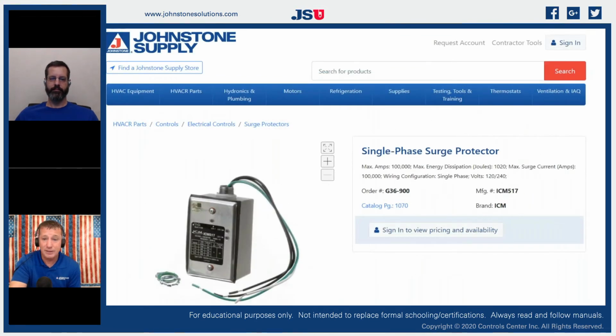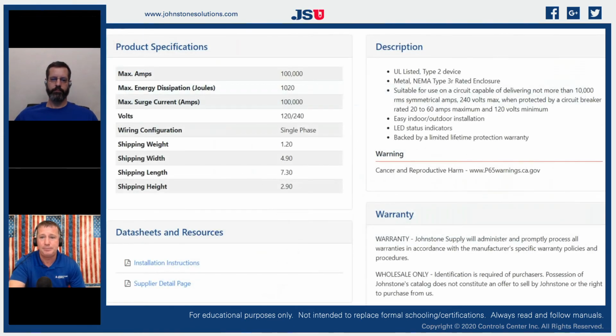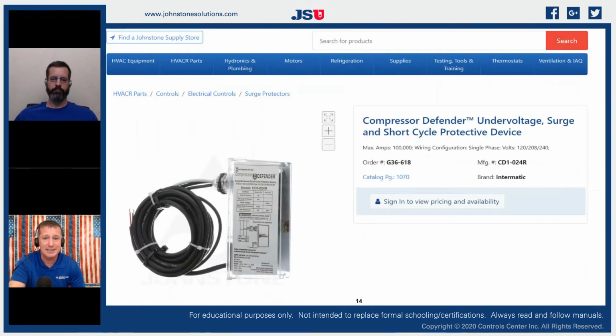Now, there's a lot of different surge protectors out there that still have high voltage capabilities. So there's also that ICM 517. That one's still got 100,000 maximum amp control to it. It's rated at 120 or 240. So it's just a more compact unit. We sell a lot of these for air handlers and for furnaces. So it's a simple add-on component. And it's rated up to 60 amps.